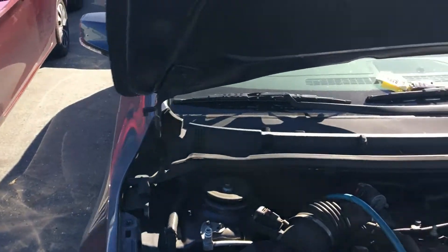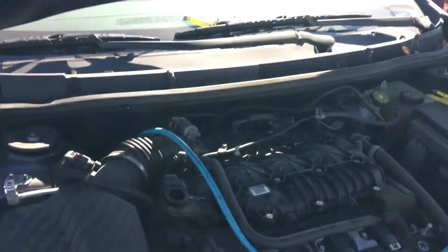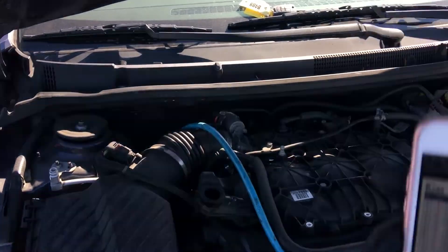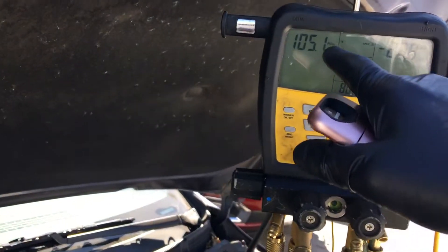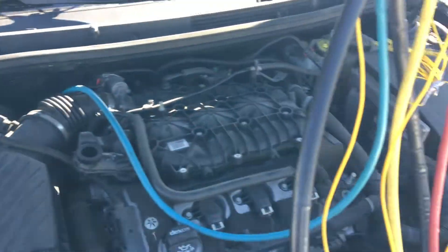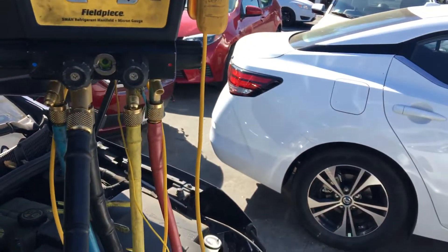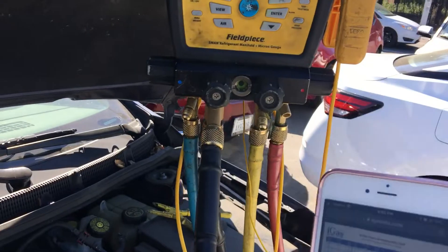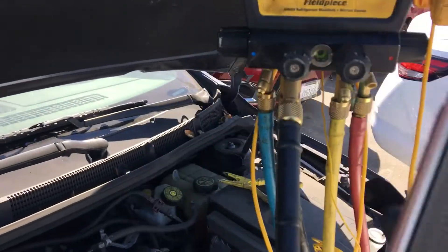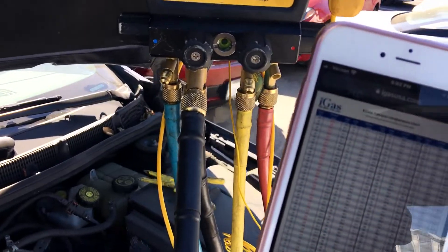If you open the windows and doors and let the car sit overnight in a garage out of the sun, you could come close to telling whether or not the refrigerant is pure, because it would be like a contained vessel without different temperatures in different places. But as for temperature-pressure chart relationships — same thing for split systems in residential or commercial. You could have evaporators downstairs in a building that's 72 degrees, but a condenser on a roof that's 102 degrees. How are you going to take a pressure-temperature measurement of the whole thing as an average to determine if the system is pure?